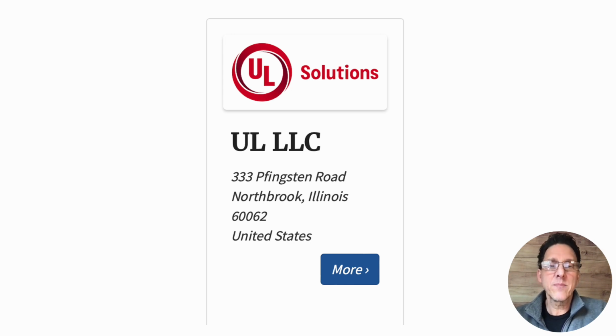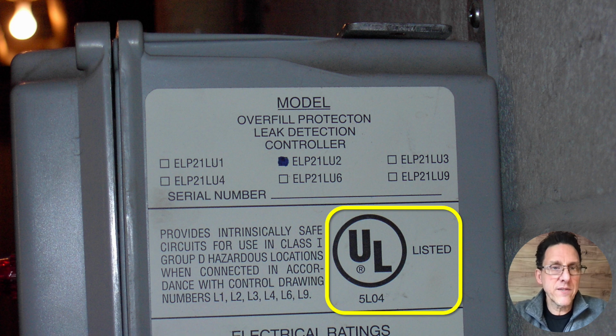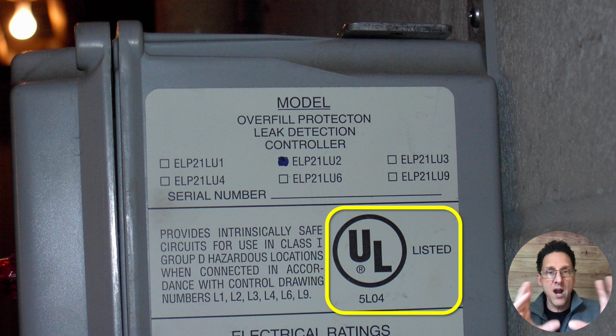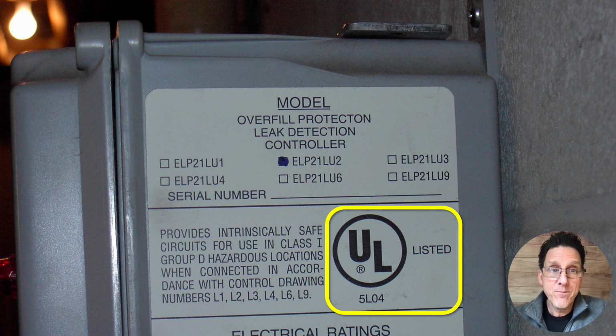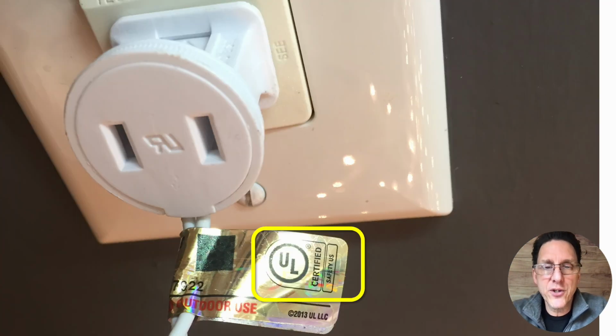Now let's take a look at some markings on actual equipment. Here's a piece of equipment. It's a leak detection controller. It's UL listed. There's the UL mark. It says it's UL listed. Okay. Now here's another piece of equipment. It has the UL mark, but it doesn't say listed. This one says UL certified.